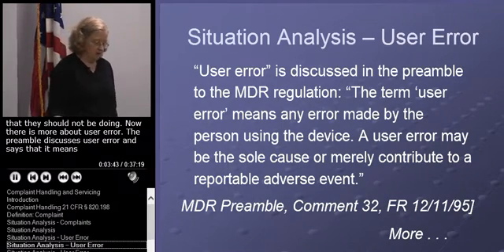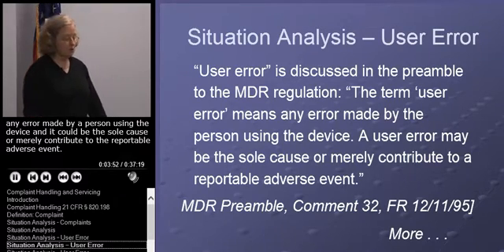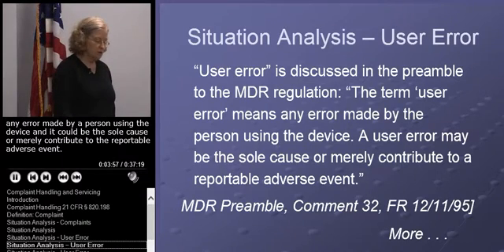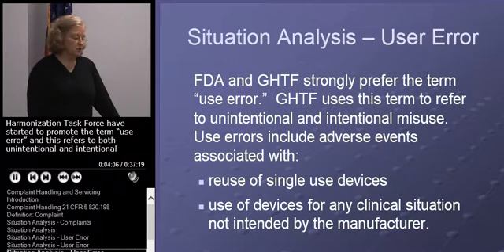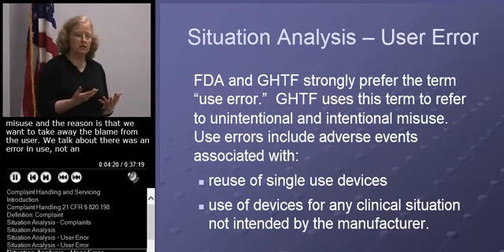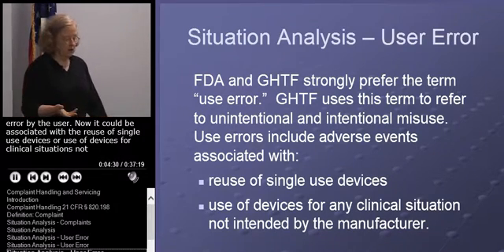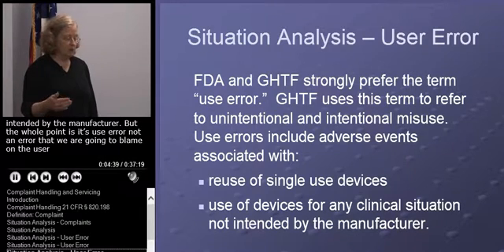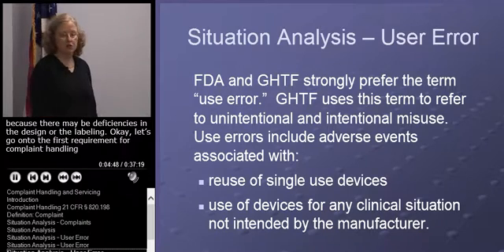There's more about user error. The MDR preamble discusses user error and says it means any error made by a person using the device, and it could be the sole cause or merely contribute to the reportable adverse event. FDA and the Global Harmonization Task Force have started to promote the use of the term 'use error,' which refers to both unintentional and intentional misuse. The reason is we want to take away the blame from the user — we talk about an error in use, not an error by the user. It could be associated with reuse of single-use devices or use of devices for clinical situations not intended by the manufacturer. The whole point is it's use error, not an error we're going to blame on the user, because there may be deficiencies in the design or the labeling.